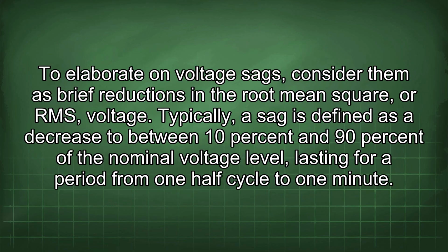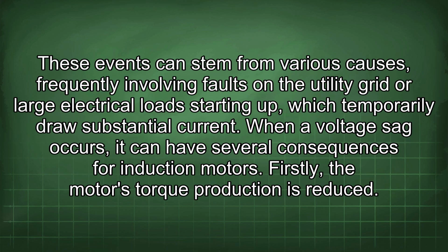To elaborate on voltage sags, consider them as brief reductions in the root mean square, or RMS, voltage. Typically, a sag is defined as a decrease to between 10% and 90% of the nominal voltage level, lasting for a period from 1/2 cycle to 1 minute. These events can stem from various causes, frequently involving faults in the utility grid or large electrical loads starting up, which temporarily draw substantial current.